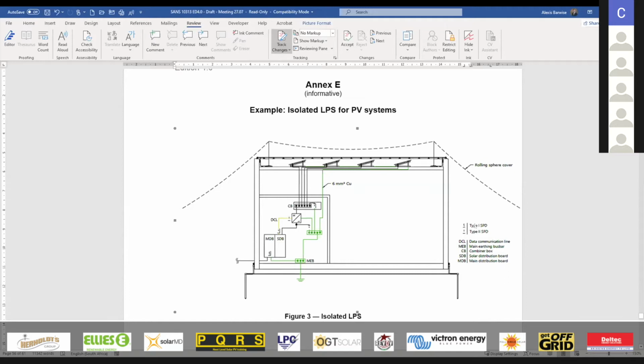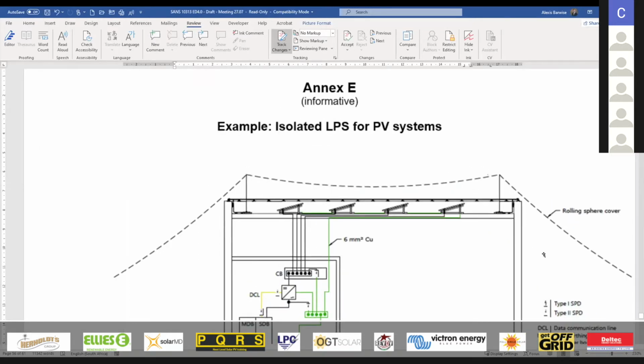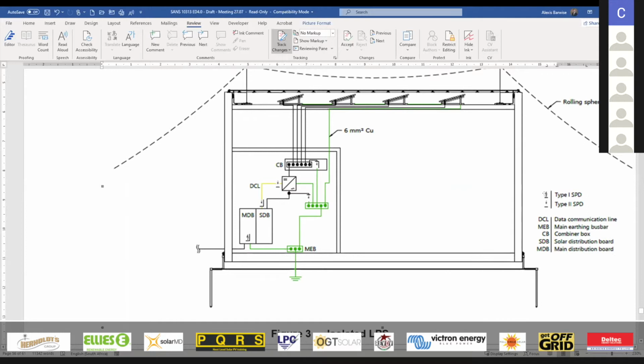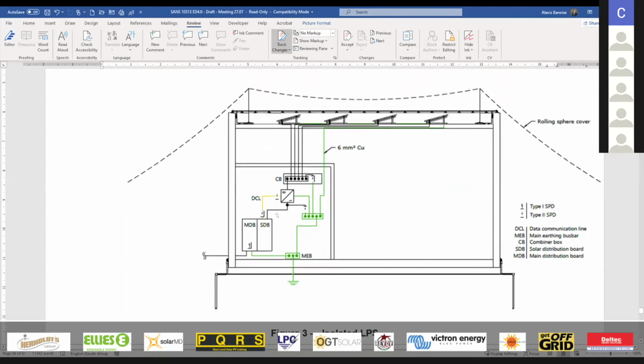And then the SPDs to be fitted. There's a clear guideline: a type 1 has a lightning strike in it, the type 2 only has a triangle. You can see here we would only require type 2 SPDs on the DC and AC side of the inverter, and type 1 on the main DB, because we still don't know what Eskom could be bringing in from the other side. But a main DB type 1, type 2 combination is already quite a standard practice.